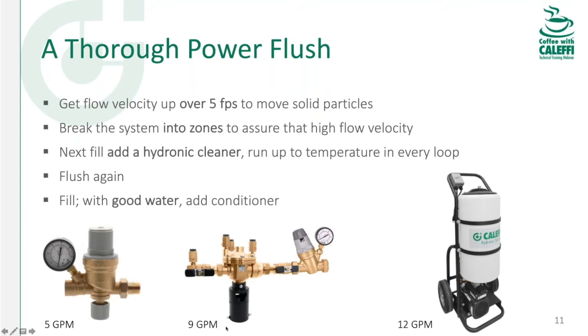If you need more horsepower, Caleffi has a half-horsepower fill-purge cart that goes up to about 12 gallons per minute and can pump up to about 80 PSI. For a good blast on a small geo system, that purge cart works well. You can mix chemicals in it — blend glycols on the job site, put some cleaners in, run it for a couple of hours, then come back and flush it out. It's a multi-function tool that also works as a cleaning device.